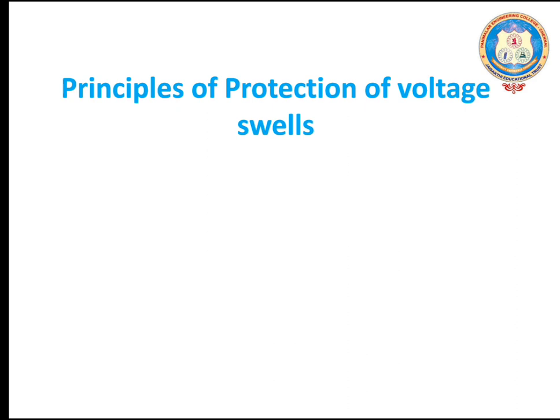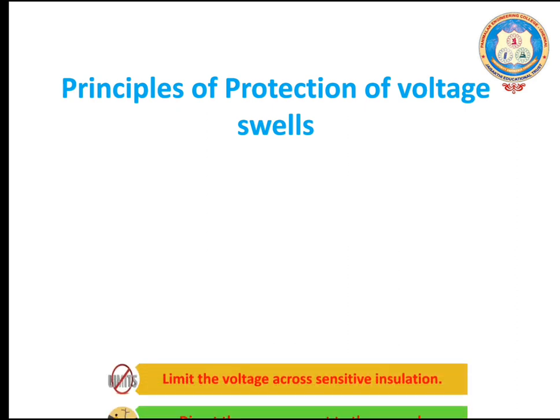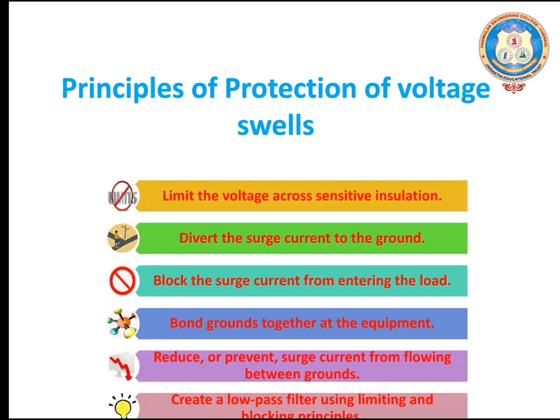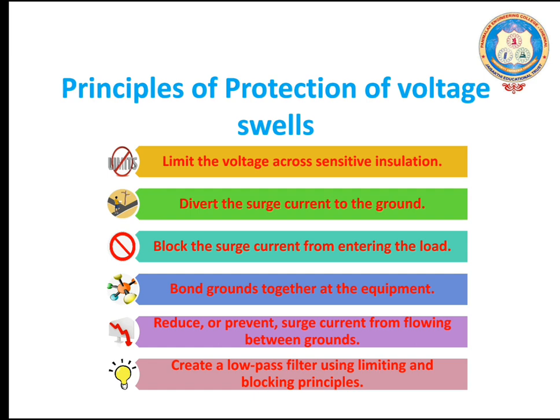What are the principles of protection of voltage swell? Limit the voltage across the sensitive insulation by diverting the surge current to the ground, by blocking the surge current from entering the load, by bonding grounds together at the equipment, by reducing or preventing surge current from flowing between grounds, by creating a low-pass filter, and by using limiting and blocking principles.